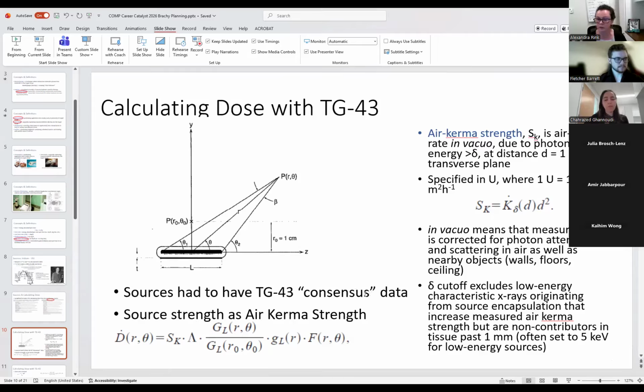So I'm just going to quickly talk about what the equation is. This is the dose rate at any point around the source, at a distance r and an angle theta with respect to the line of the source. And all of these values are source specific and calculation specific, and I'll cover that in a second. So when I, as a physicist, get the source for iridium-192, all I'm actually checking is that the specified air kerma strength from the vendor is as expected. I'm not going to go into the methodology of how I check that, but it is one of our jobs to make sure that the strength of the source matches what the vendor tells us it is.